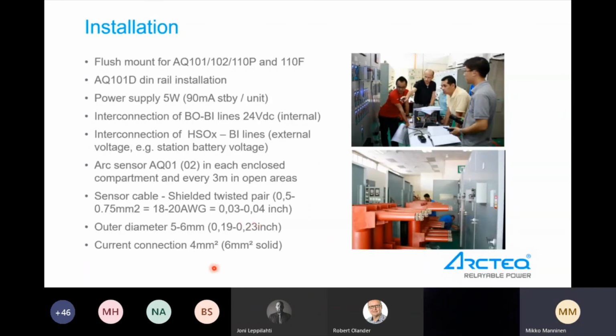There are some examples of the sensor cable. Arc sensor in each enclosed compartment and every 3 meters in open areas. Sensor cable is typically this size. Current connection is 4 square millimeter, and sometimes it is also very common to use 2.5. But 4 square millimeters is very good for this.